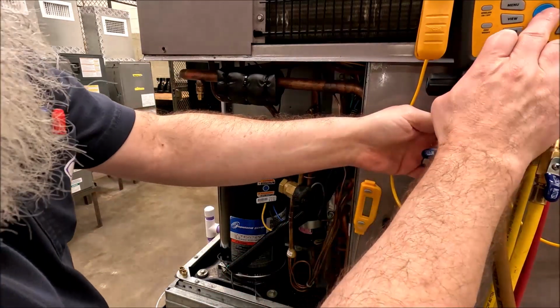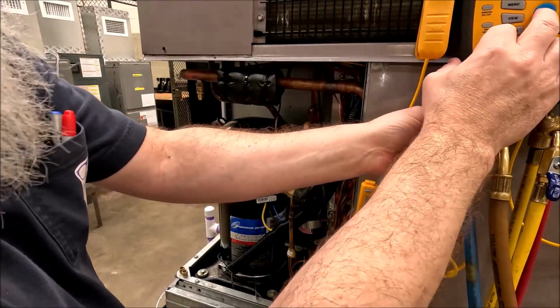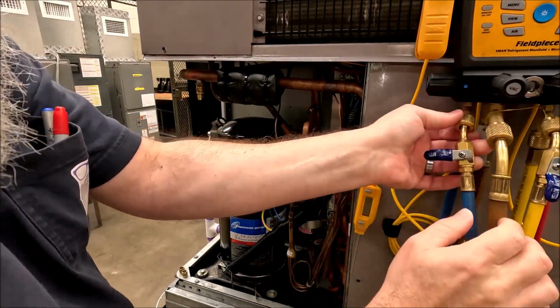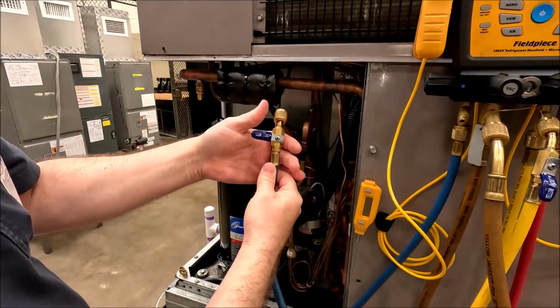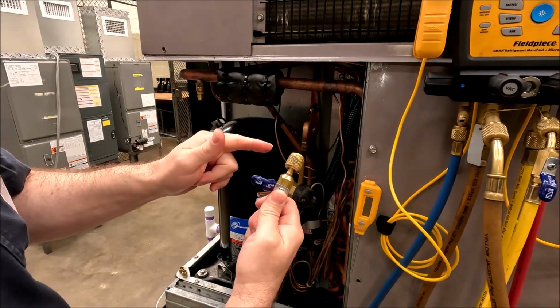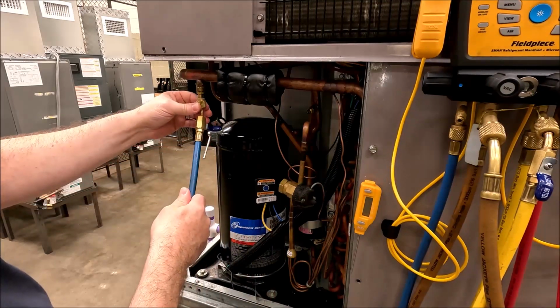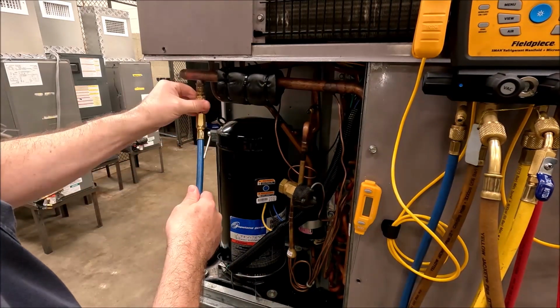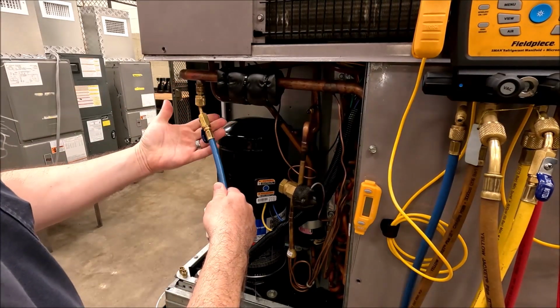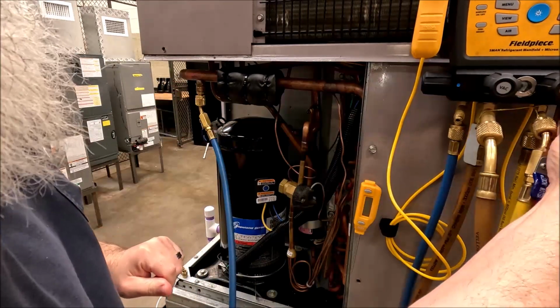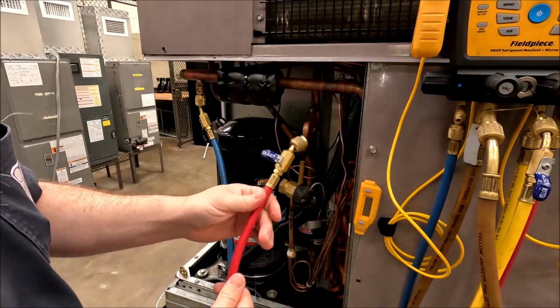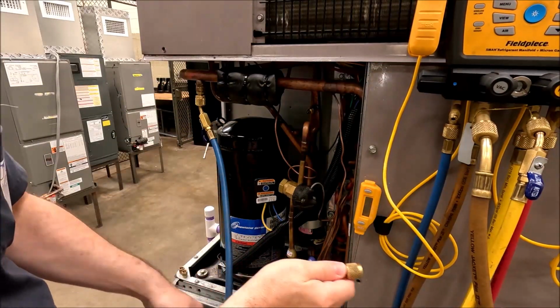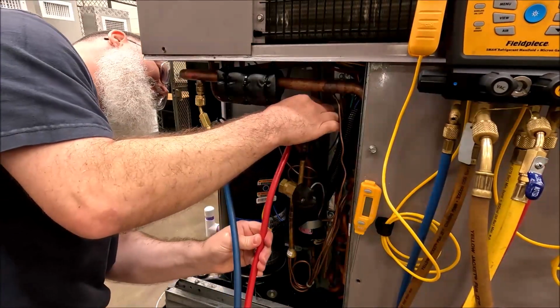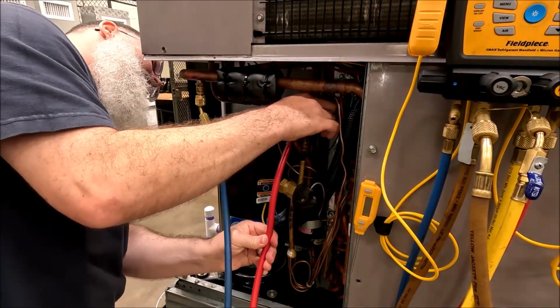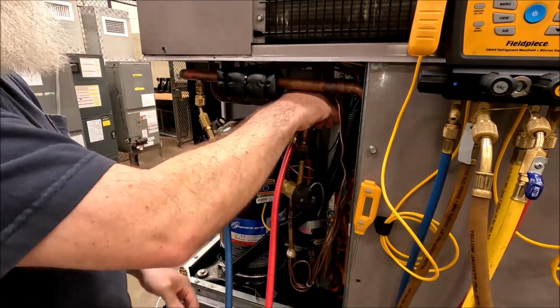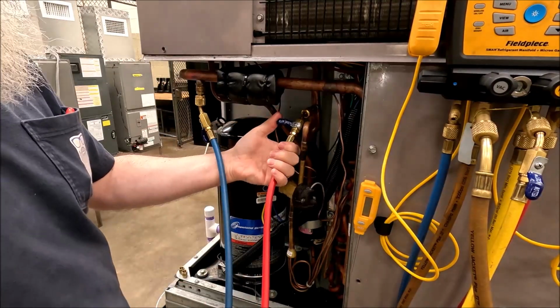So I'm gonna turn my gauges on. There we go. I'm gonna take my low pressure. I've got some refrigerant in there, so I'm not going to open this up. I'm going to put that on, open the valve for my low loss feature. I'm going to take this one, high side, that's going to be on my discharge. There we go. Turn it on.